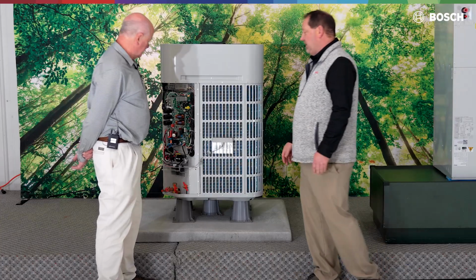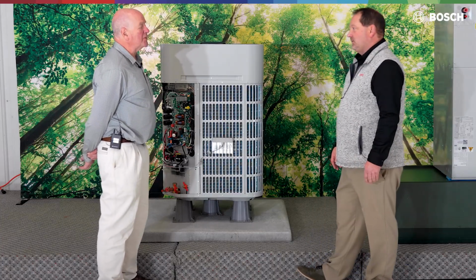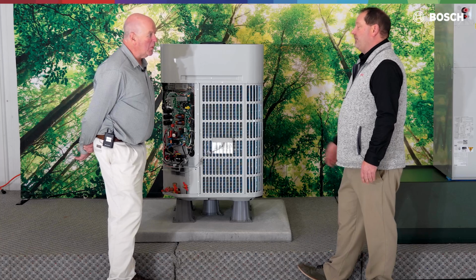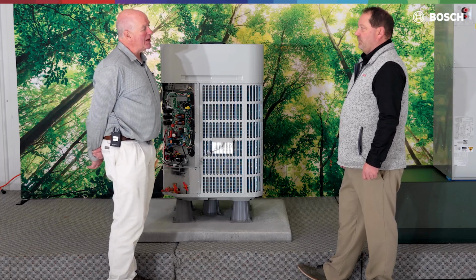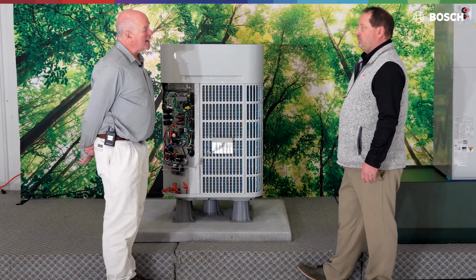All right. Okay. So our suction line, the hot gas line, needs to be insulated. Okay. The liquid line doesn't have to be. It doesn't hurt, especially if you're putting this in an attic area that's unventilated.